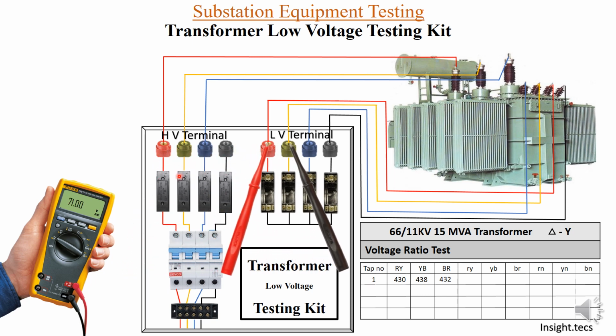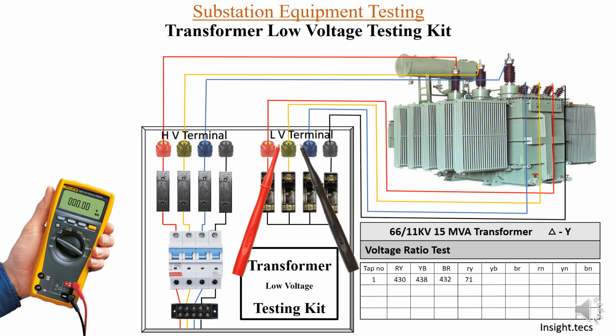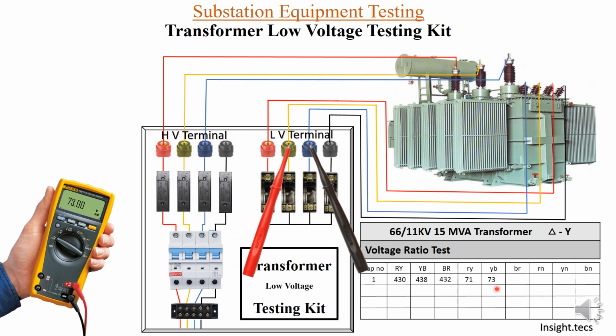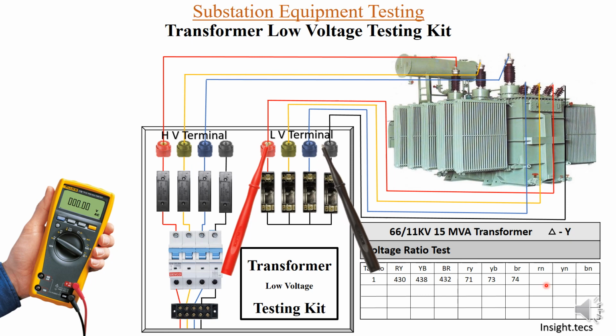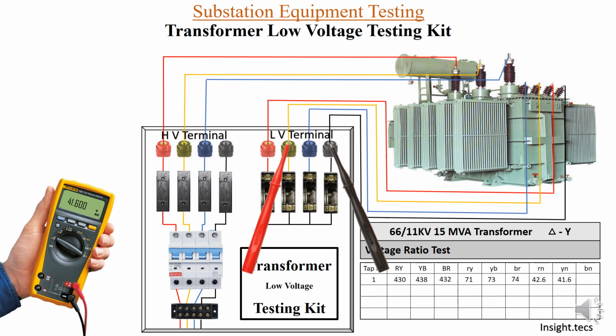Between LV terminals R and Y phase the voltage is 71 volts. So we will note it down, 71 volts. Similarly, for YB phase we have 73 volts, and BR phase voltage is 74. Now let us measure the voltage between phase and neutral. R phase and neutral voltage is 42.6 volts. Y phase and neutral is 41.6 volts. Thirdly, between B phase and neutral the voltage is 41.5 volts.